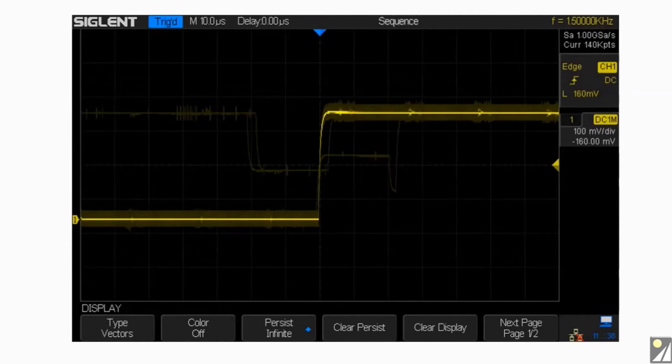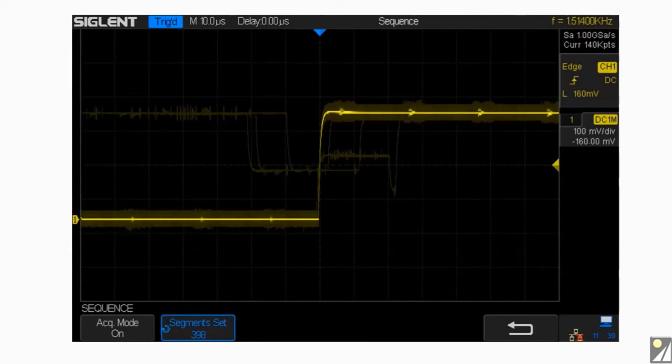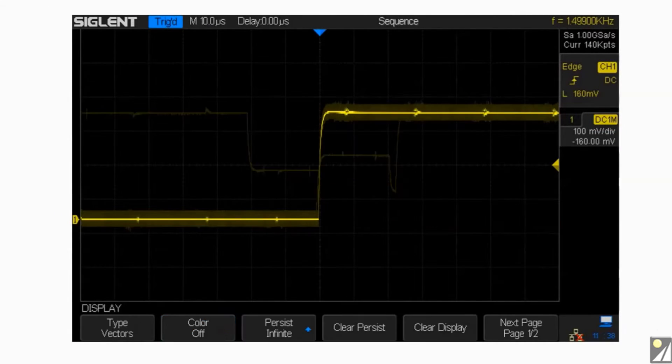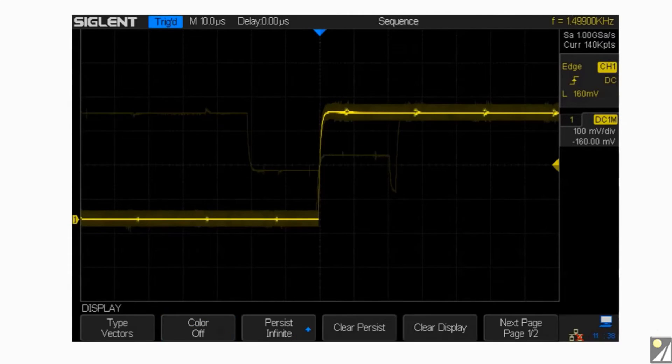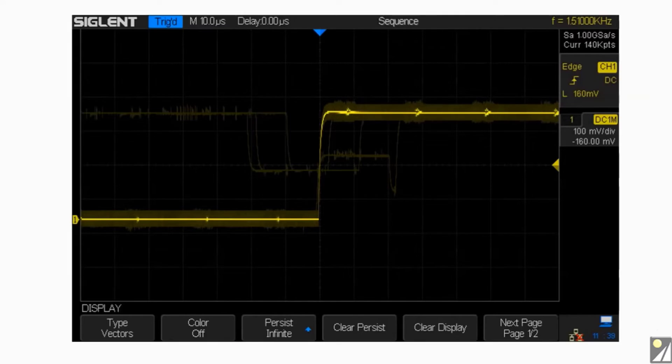The SDS-1000X also has a sequence function which will store the waveform into multiple memory segments. Each segment stores both the triggered waveform and dead time information.